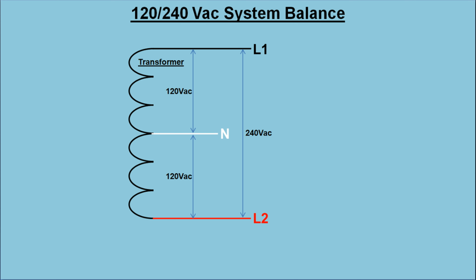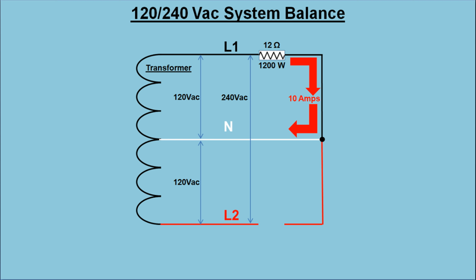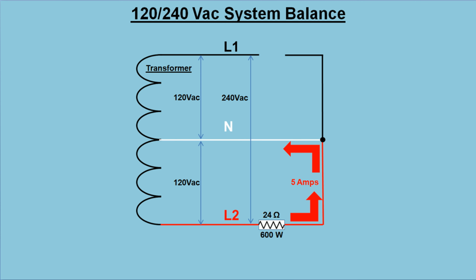The diagram shows a 120-240 volt transformer with a black line 1, a red line 2, and a white neutral. Line 1 to line 2 is 240 volts AC. Line 1 to neutral is 120 volts AC, and line 2 to neutral is 120 volts AC. If we put a 120 volt 1200 watt load on line 1 to neutral, with line 2 being open, the neutral will have 10 amps flowing through it. If we put a 120 volt 600 watt load on line 2 to neutral, with line 1 being open, the neutral will have 5 amps flowing through it.